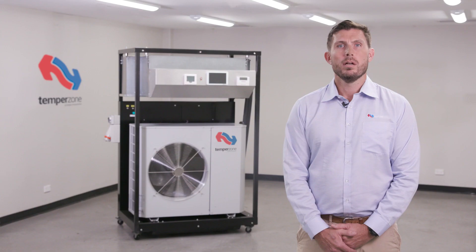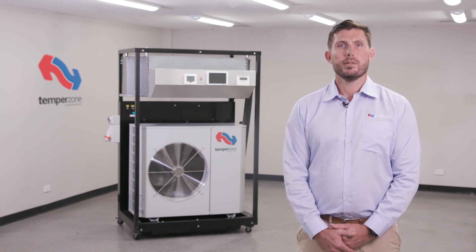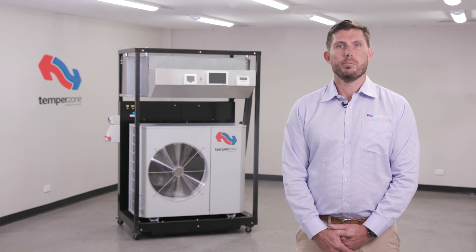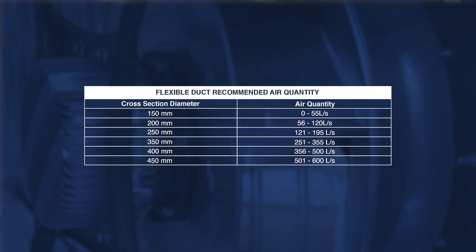Units with short return air plenums will often show two circles of debris on the indoor coil after many hours of operation. Flexible duct is limited to the volume of air it can deliver by its cross-sectional area. Design flexible ducting so that the duct selected can supply the nominal airflow of the unit.